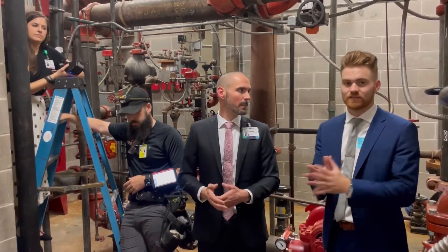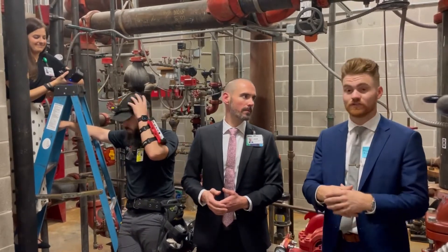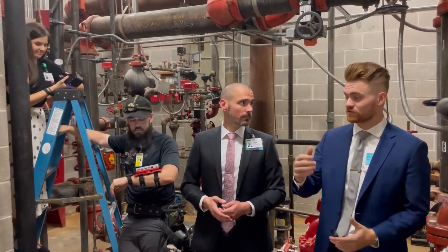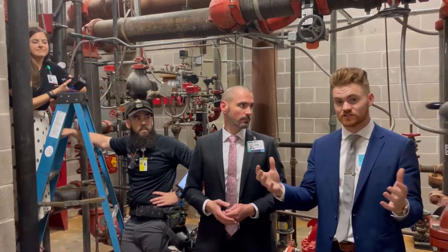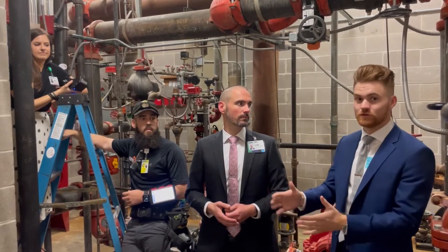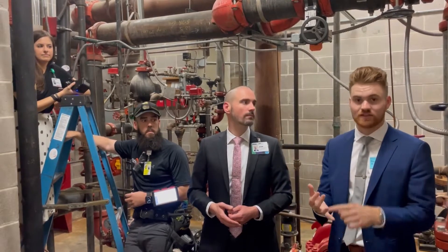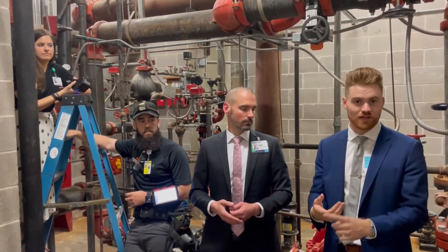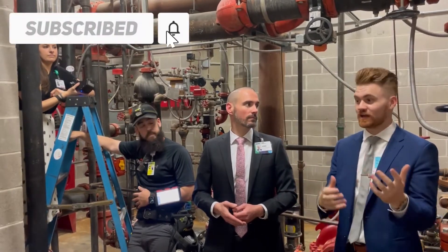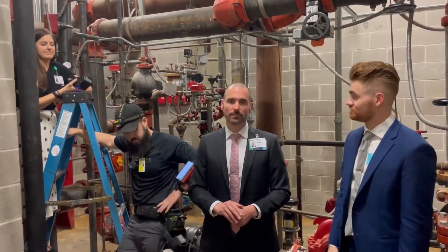We're also getting consistent readings across our entire hospital portfolio. With traditional inspection, there's a chance of only getting a check valve done or getting the whole system inspected — it varies contractor by contractor. We've created a standardized approach: a six-point location inspection on each system assessing wall thickness, corrosion, sludge, slime, microbiologically influenced corrosion (MIC), and air-water tracking.